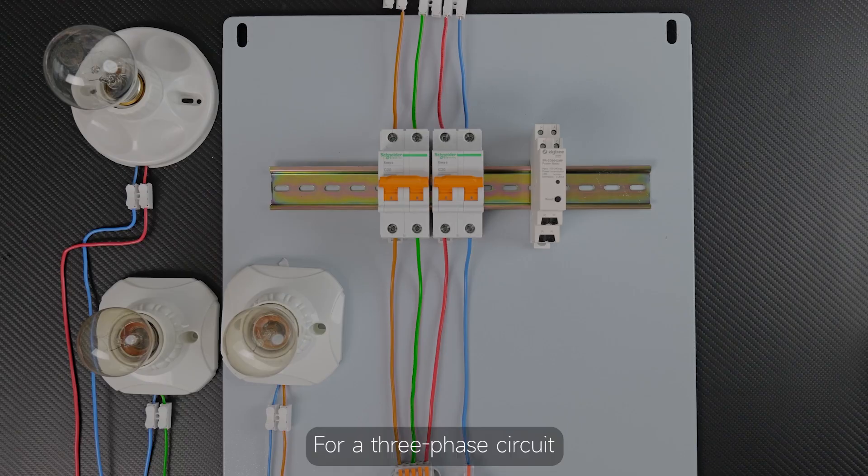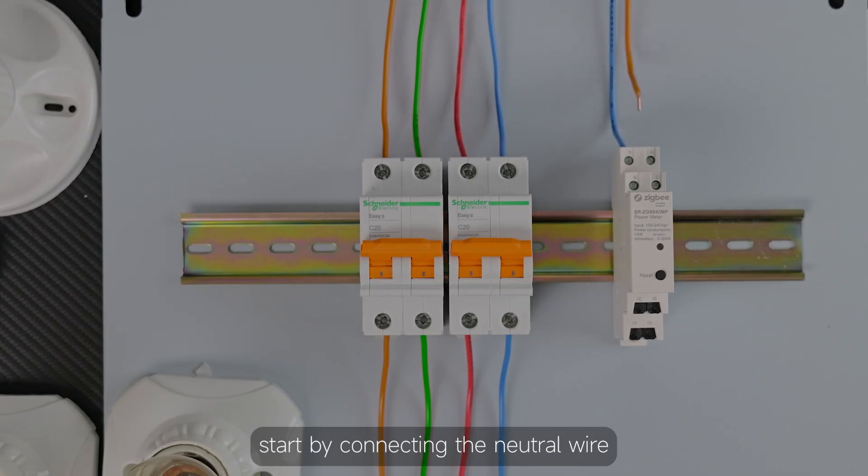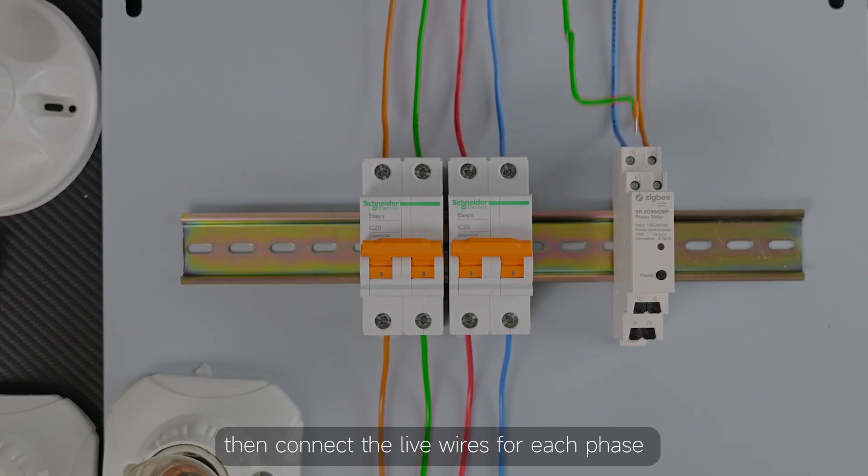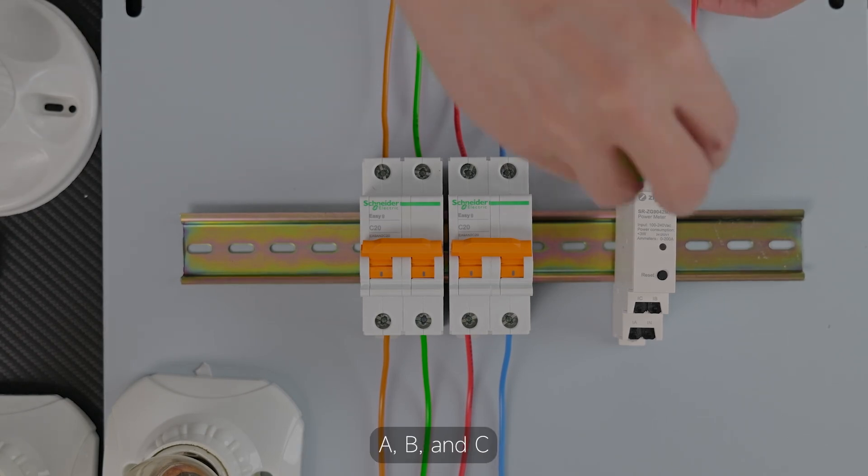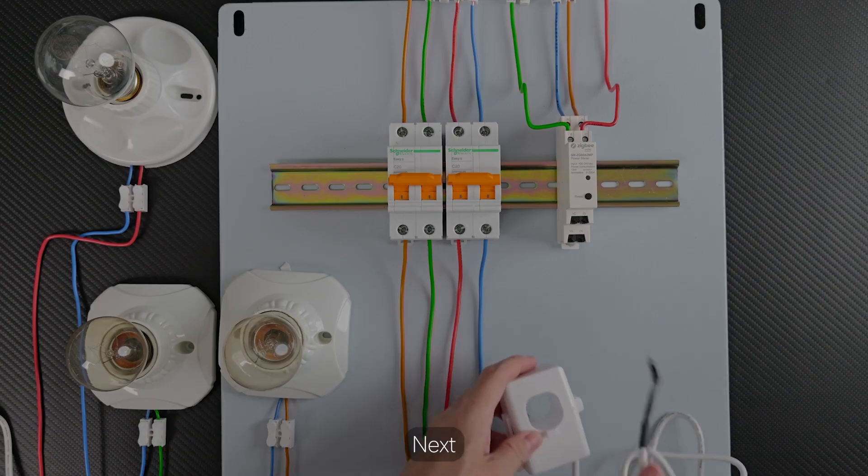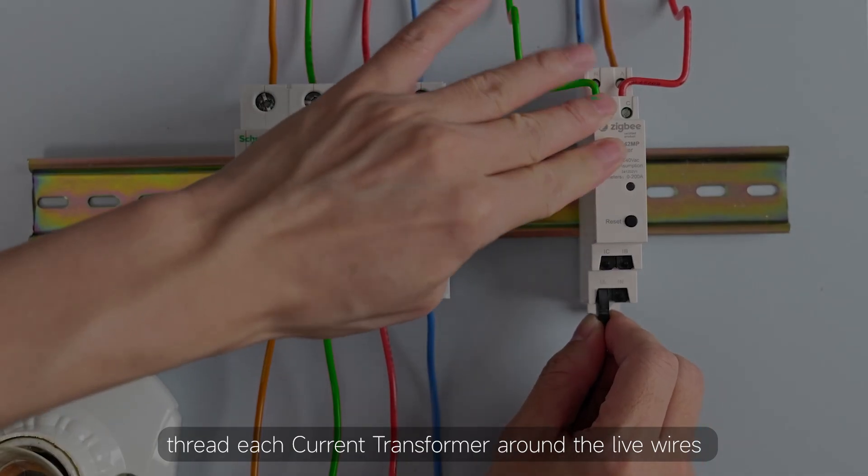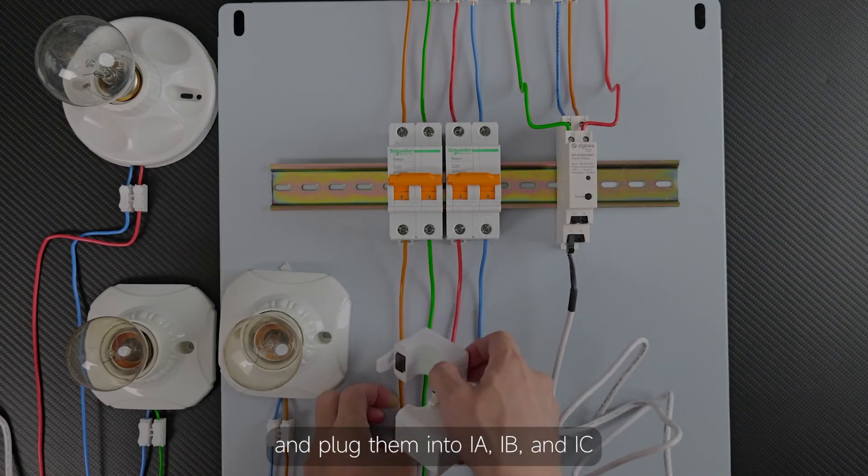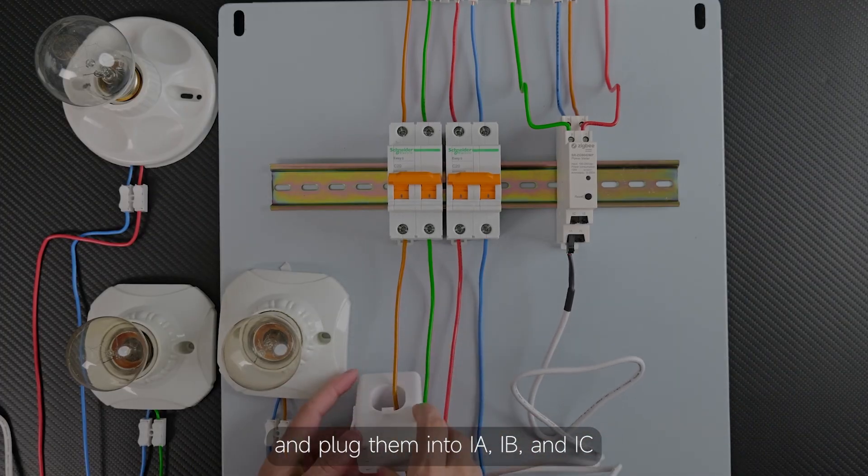For a three-phase circuit, start by connecting the neutral wire, then connect the live wires for each phase to the corresponding ports A, B, and C. Next thread each current transformer around the live wires and plug them into IA, IB, and IC.